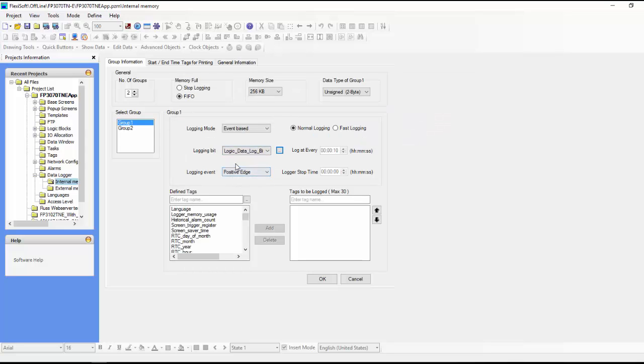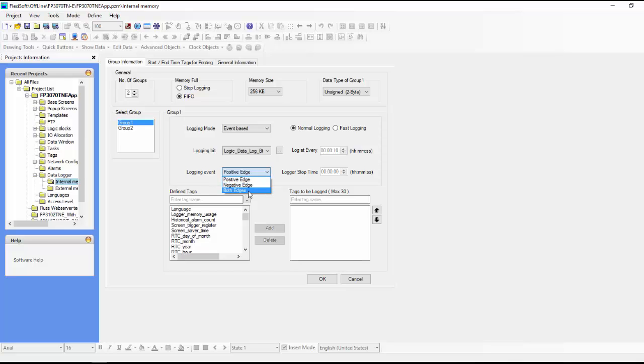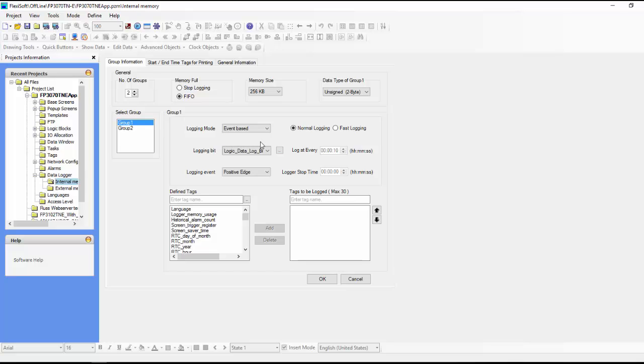So now with this setting, on every positive edge of that bit turning on, we create a log. So you can do negative edge or you can do both edges. Usually most people do positive edge. So this bit can be controlled in logic or can be controlled by the screen or wherever you want to.